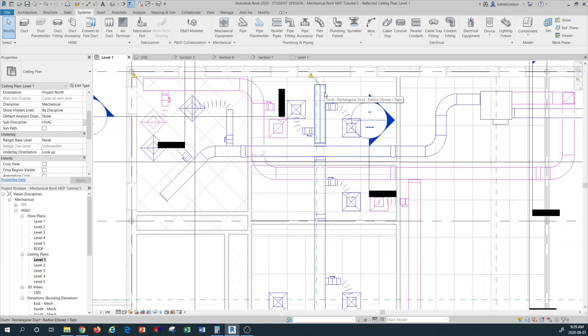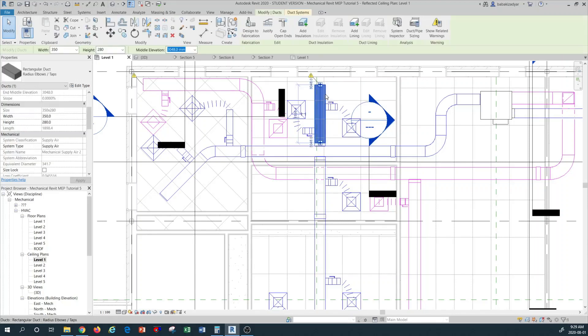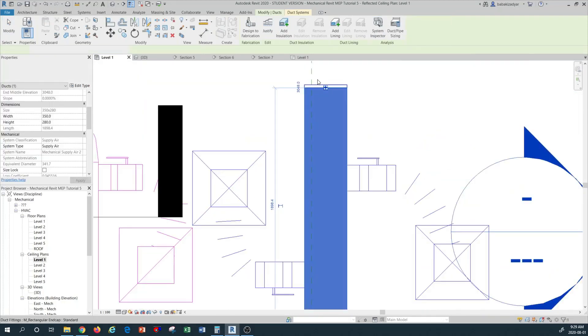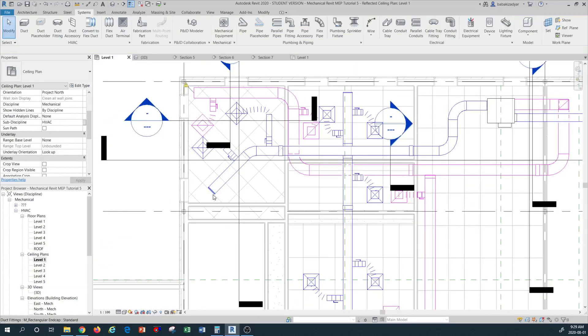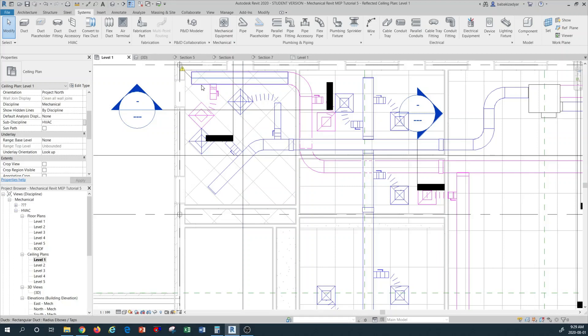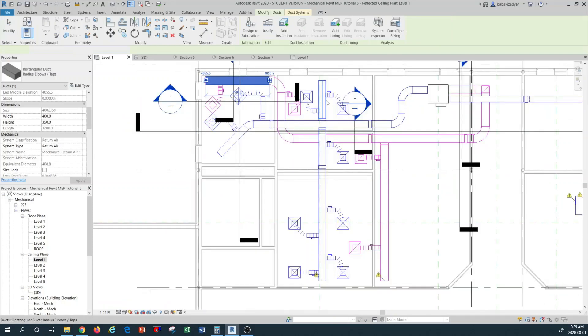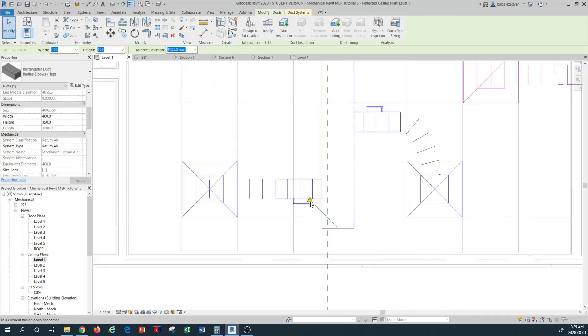I'm going to hover on any of the duct main distribution ducts that have an open-ended branch. Left click, and this command appears at the top. I'll select Cap Open End and this is automatically closed — as you can see, this duct is closed. Doing the same thing with the other ones: this one is already capped as I showed in the previous tutorial. Hover over this one — you can see all of these little error arrows.